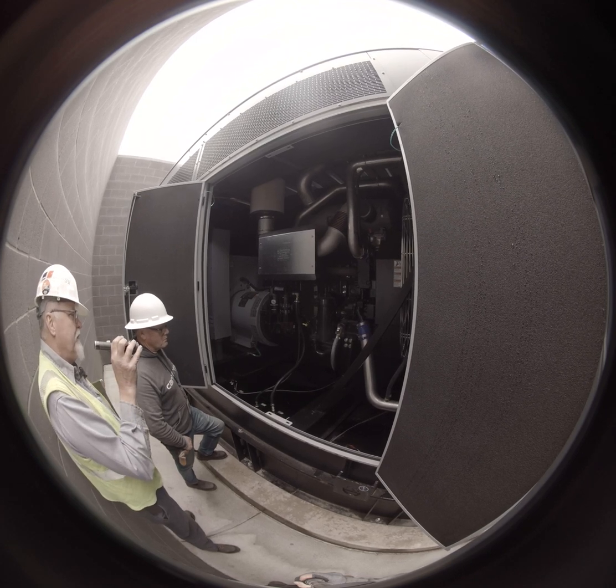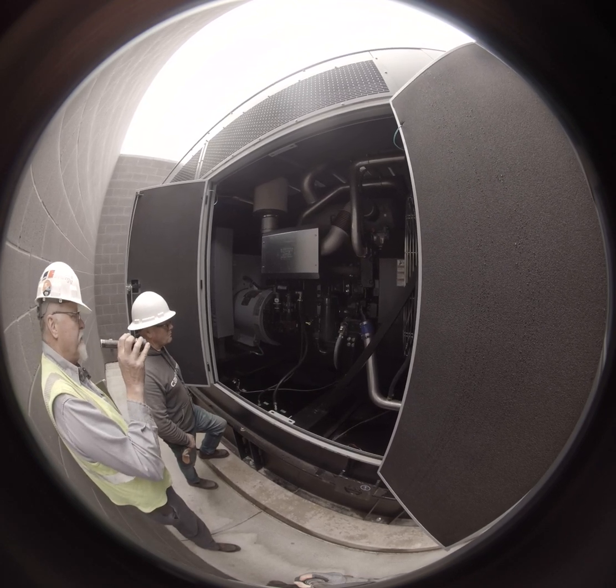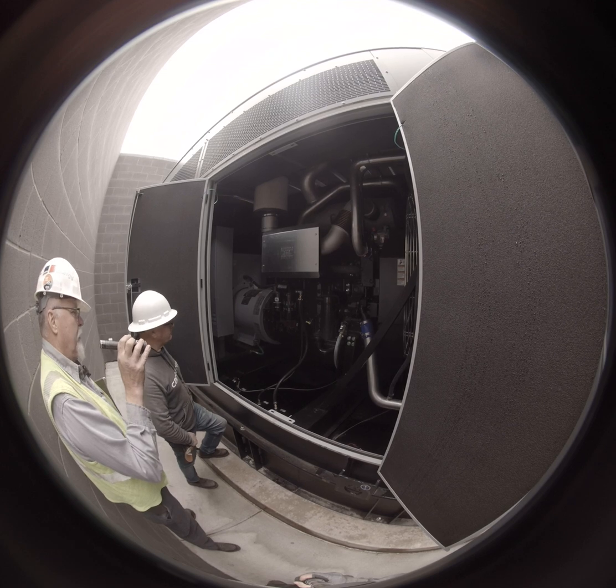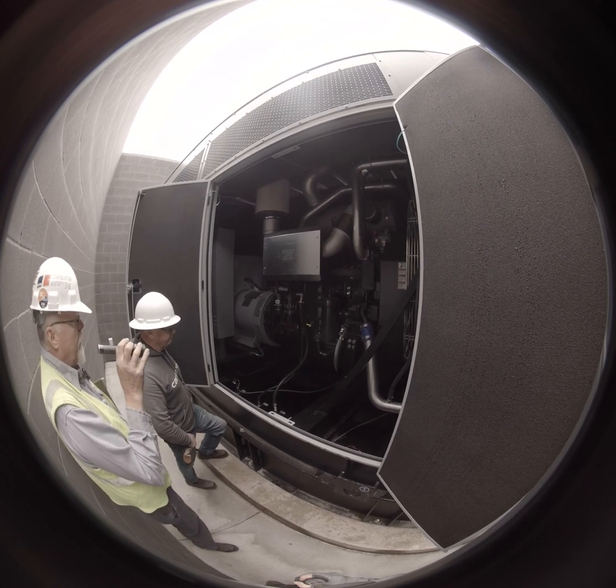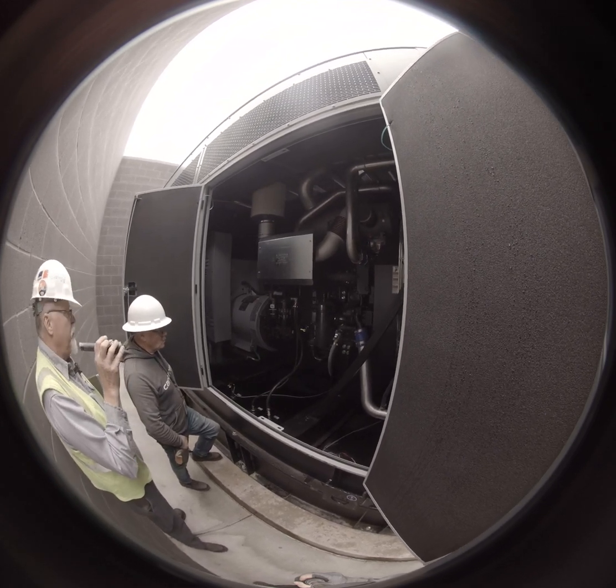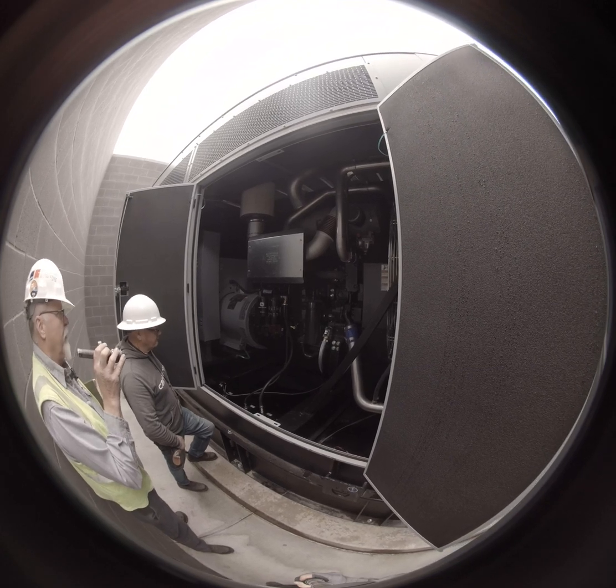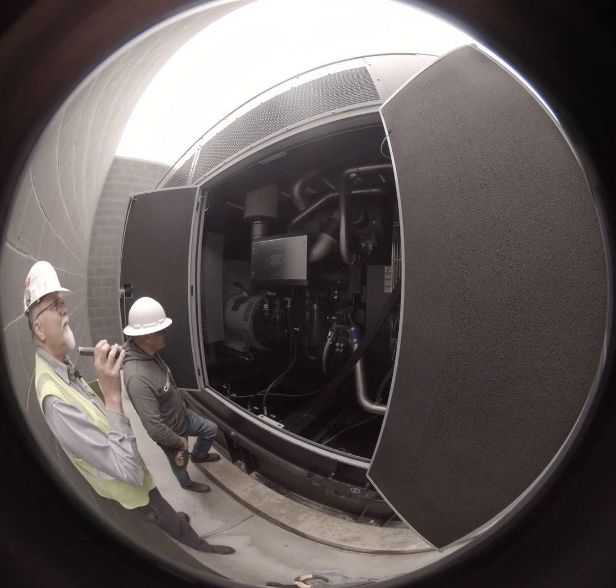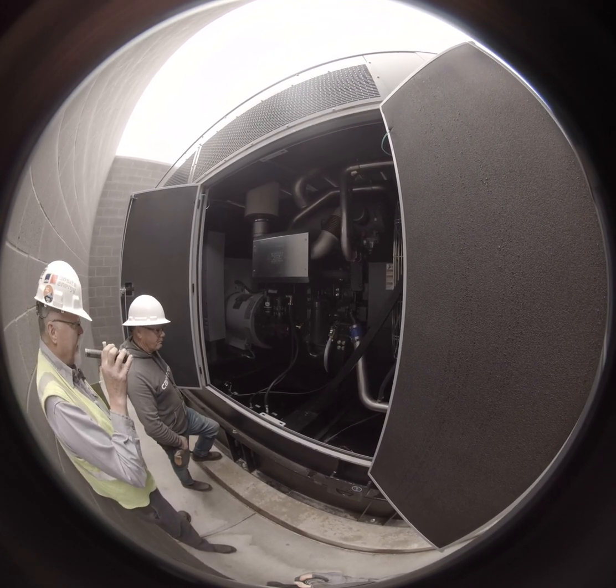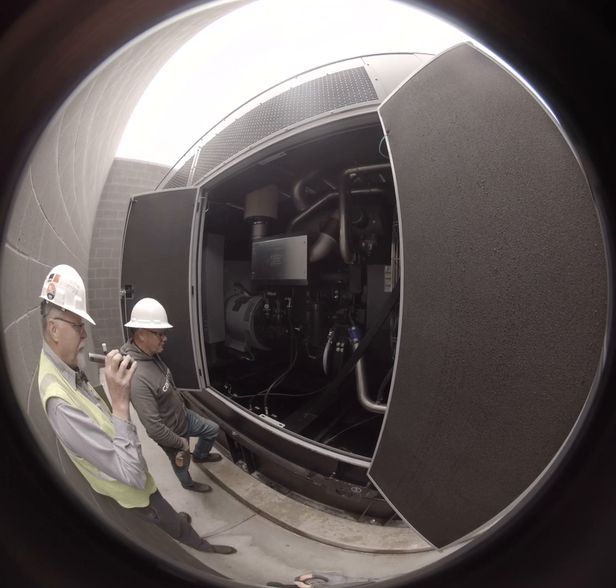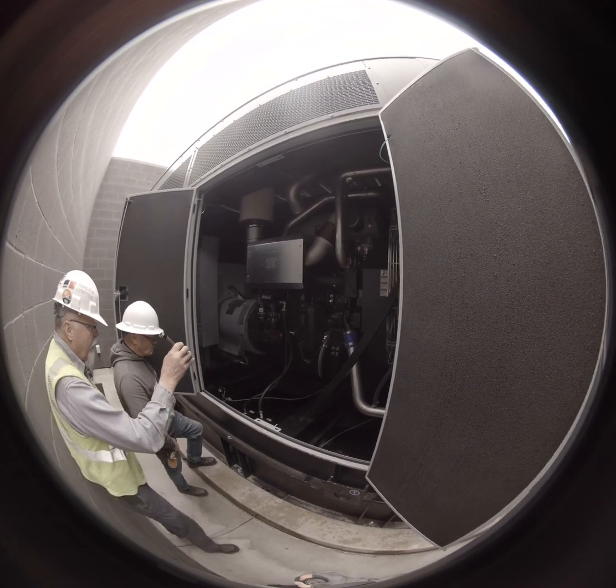So both sides of the block here on this one have shutoff valves. That way, if you need to change the hoses out, you can do it without draining the system. However, do turn off the heater before you turn off the valves, because it will superheat the heater and cause issues. Yep. Okay.